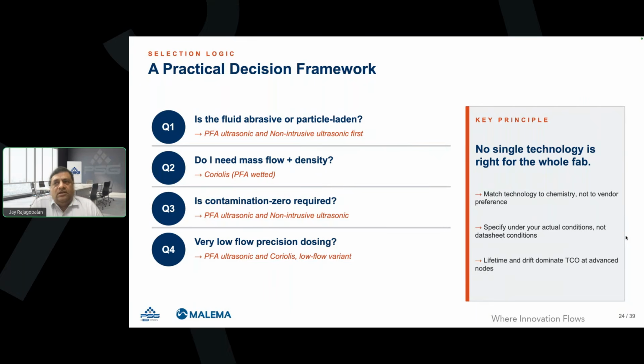Lifetime and drift have to be considered as well. Have the vendors subjected the product to a lifetime study, and how many million on-off cycles for a controller is appropriate for you? Typically, 200K to 250K cycles will equate to roughly 1 year of operation. It varies from fab to fab, tool to tool, but has the vendor done such lifetime studies? And also, what are the drift possibilities? Can the product drift over a period of time, and do we have the data? That kind of information is very valuable in selecting the right technology. Here I'm comparing three technologies and their trade-offs.